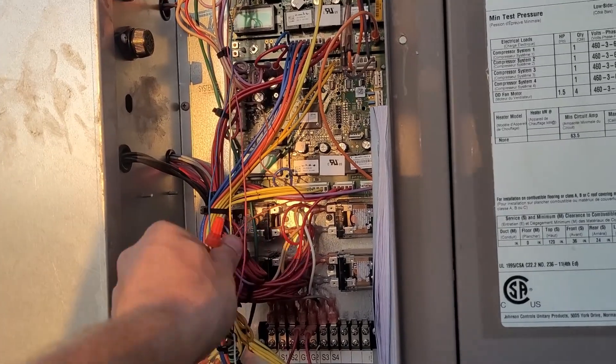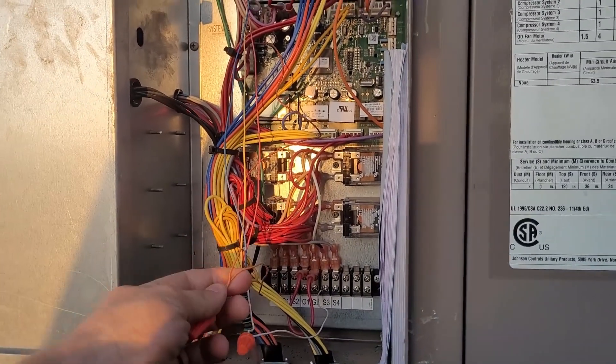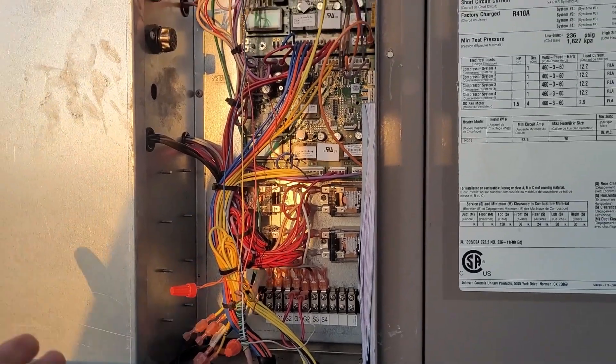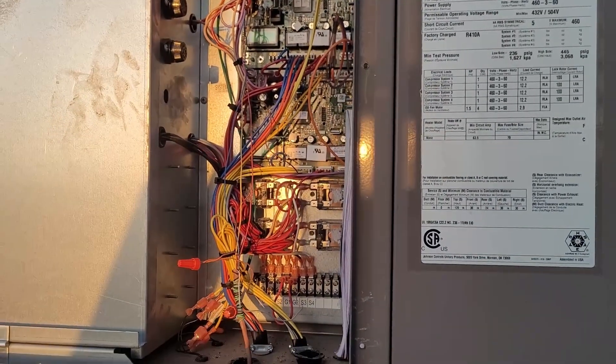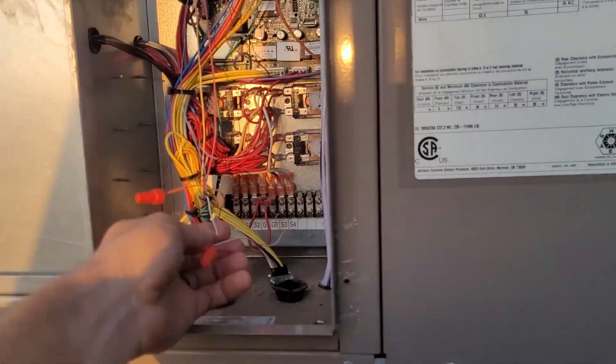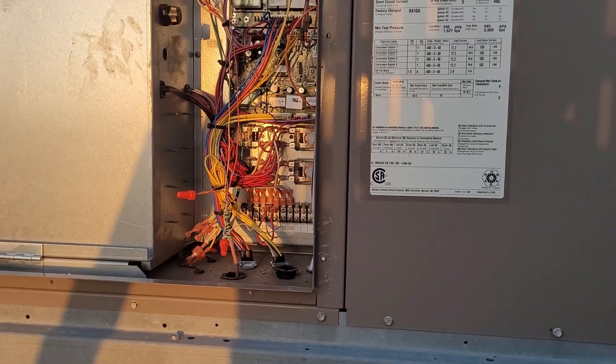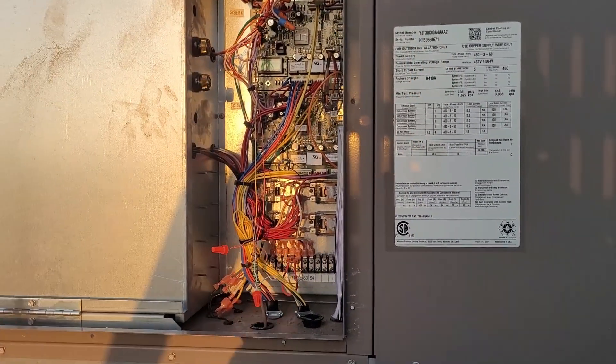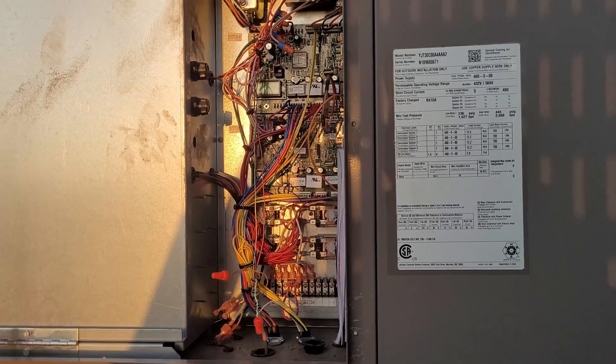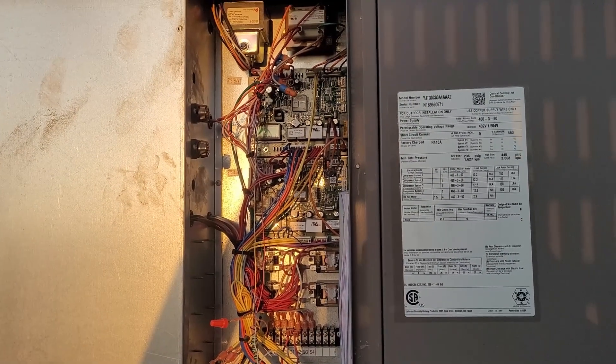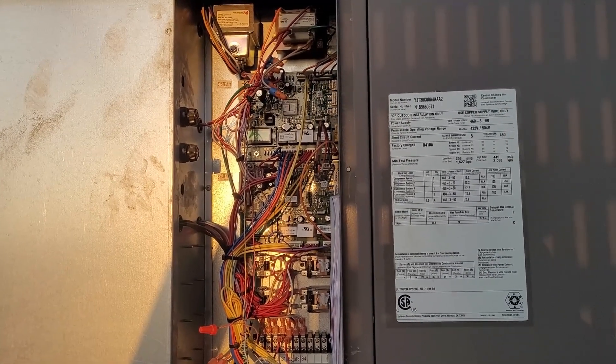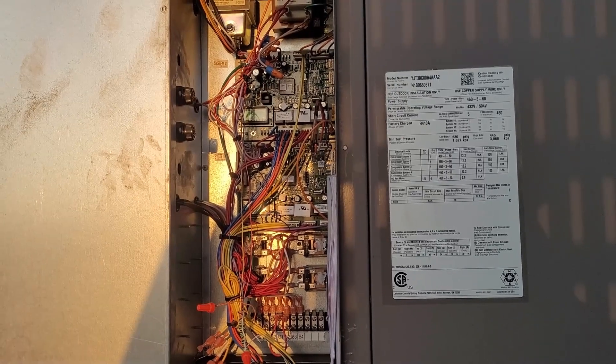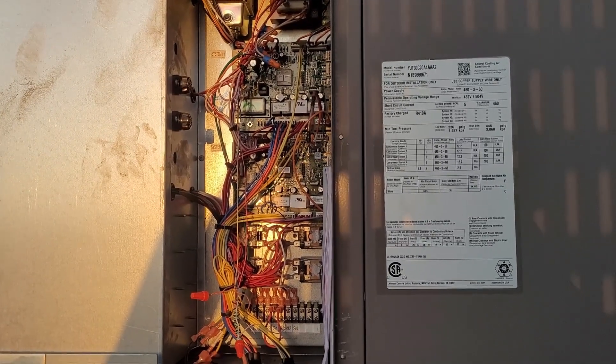Down at the controller, I've disconnected the orange wire from the yellow wire, basically, from the Y terminal and the white wire from the Y2 terminal. So that you send a call up, the board makes a decision, brings on the liquid-line solenoid, and it can time its own liquid-line solenoid just in case there's some sort of a delay that I don't know about. And now, it works.